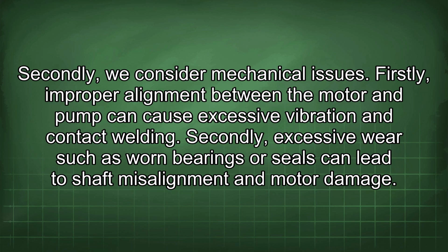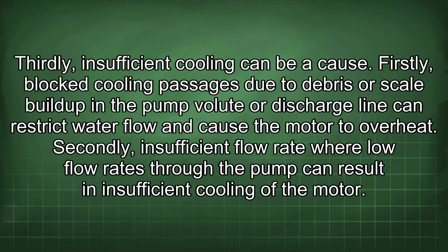Secondly, we consider mechanical issues. Firstly, improper alignment between the motor and pump can cause excessive vibration and contact welding. Secondly, excessive wear, such as worn bearings or seals, can lead to shaft misalignment and motor damage. Thirdly, insufficient cooling can be a cause.